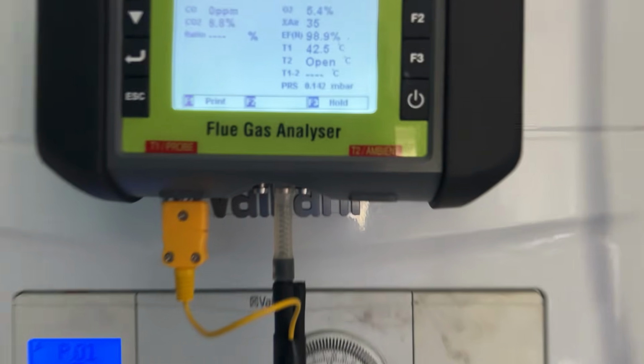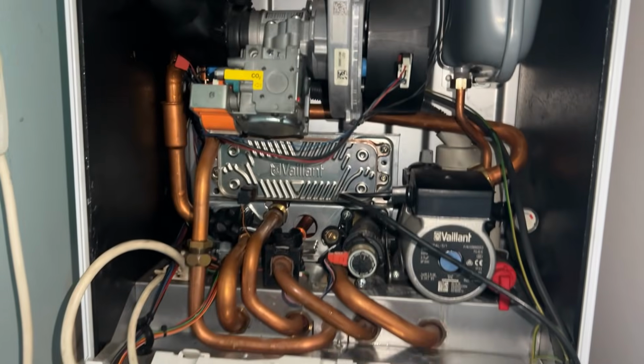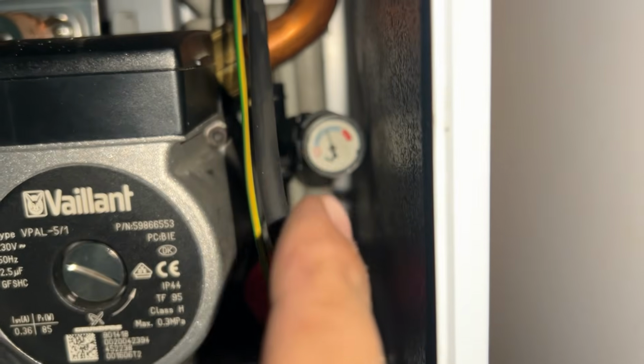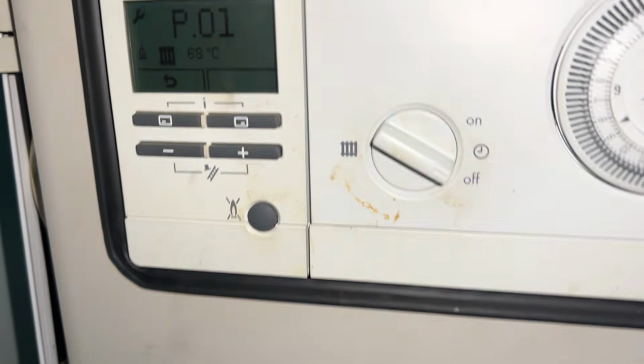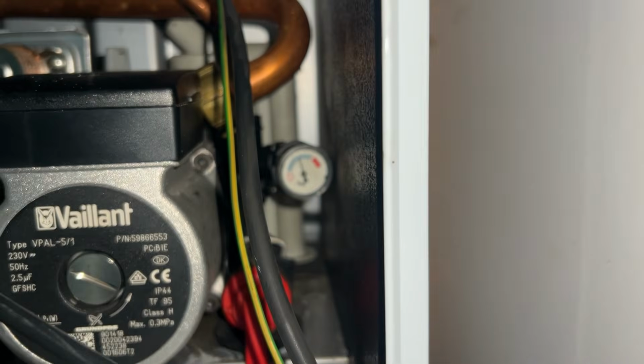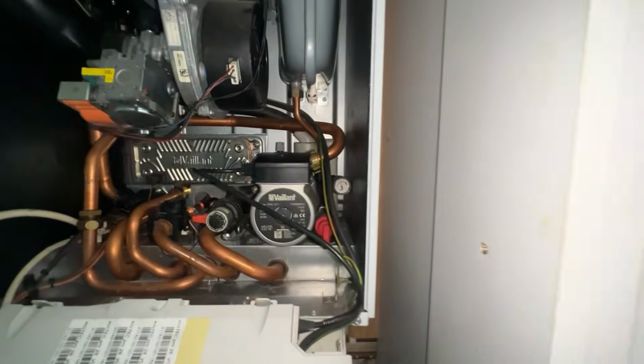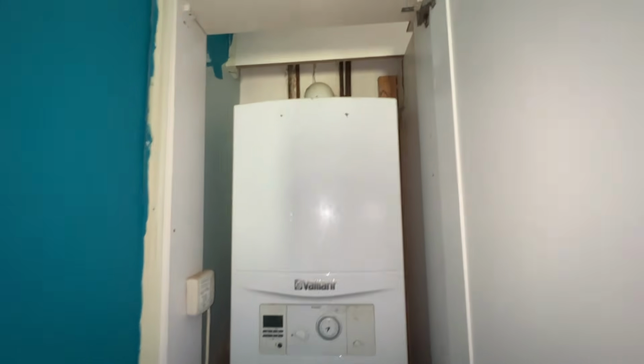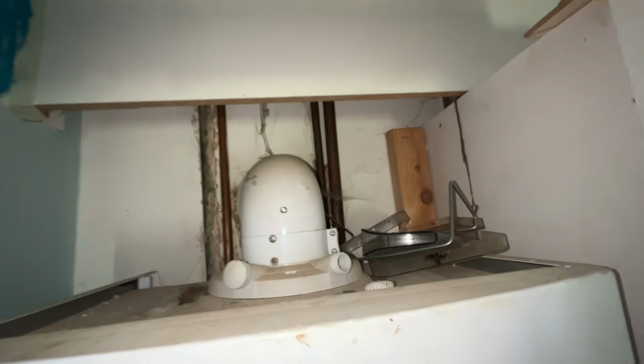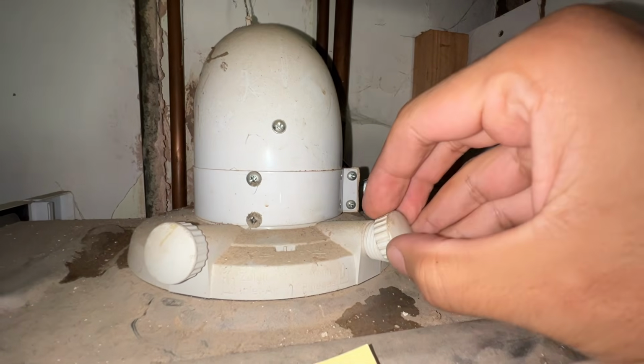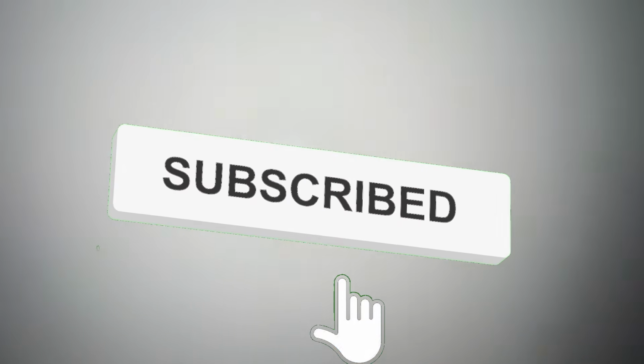Maximum, check inlet on the gas valve, and I'm going to quickly do a gas rate as well from the meter. Before I go, I'm going to check the pressure on this boiler. So it's already on 68 degrees. Pressure's, I'm not concerned about that. I would be concerned if it was closer to the red, yeah. So I'm just going to go now do the gas rate. So it's all done. Gas rate done. Gas rate is bang on. Inlet bang on. I've put my caps. No, I haven't. Caps need to go back on. Last thing to check. Make sure you double check the caps. Caps are back on. All is fine. No drips, no leaks.